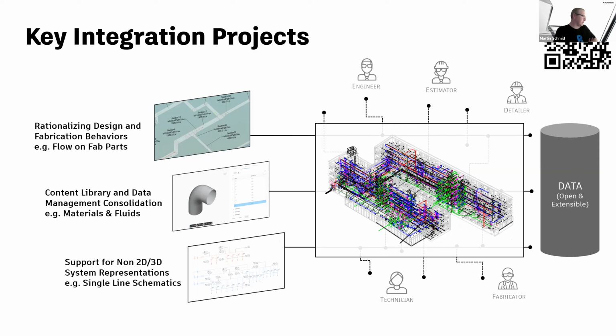With cable trays, harmonizing the way design and fabrication work might provide something you need now that you might be hesitant to jump into. With fabrication cable tray components, you can define the actual dimension versus the nominal dimension - that's a limitation of the design elements that have been there a long time, where you define a size like 12 by 4 or 300 by 600, and that's nominal but also actual within Revit. Fabrication elements provide latitude for actual versus nominal, and more flexibility, like placing them vertically on walls. We're trying to make those easier and more approachable instead of reinventing the wheel on the parts as they exist today.